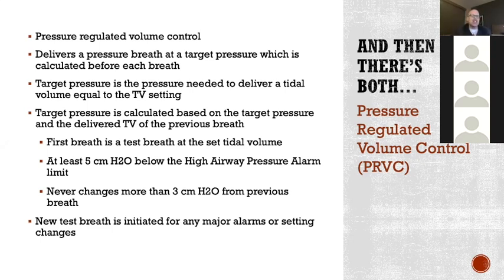And it's never going to change it drastically. It's not going to say this breath was 15 of pressure and then it gets back a little breath, oh, let's go 30 of pressure. No, it's never going to move by more than 3 typically on most ventilator models. It'll move by either 1, 2, or 3 centimeters of water of pressure.